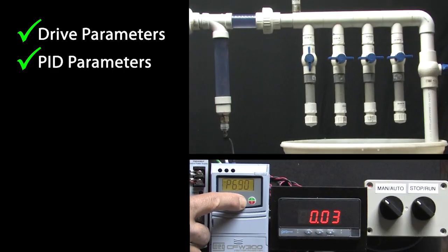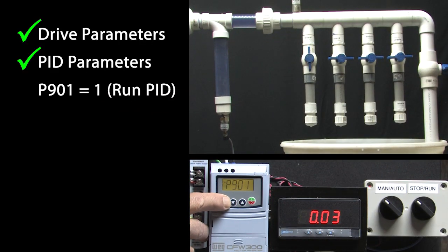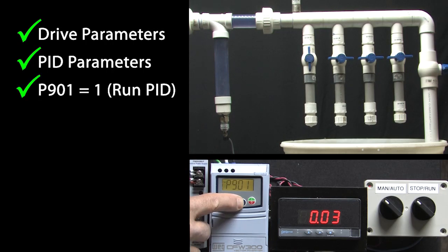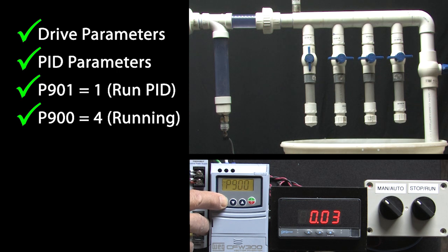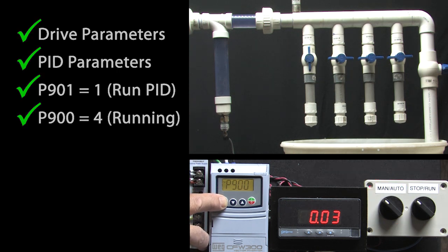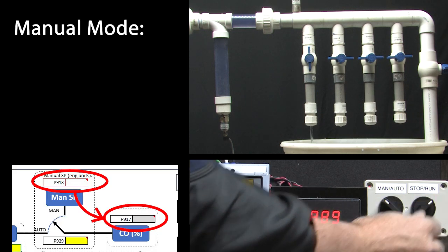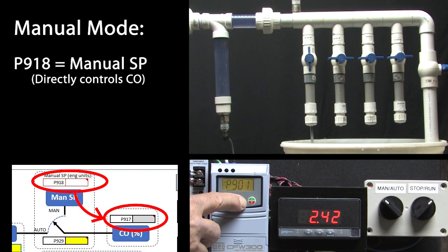Let's go to parameter 901 and set it to a 1 to tell the soft PLC PID app to run. I'll go to parameter 900 and sure enough it's a 4 which tells us the PID app is running. We are in manual mode so I'll go ahead and switch to run and go to parameter 918 and scroll through some values.